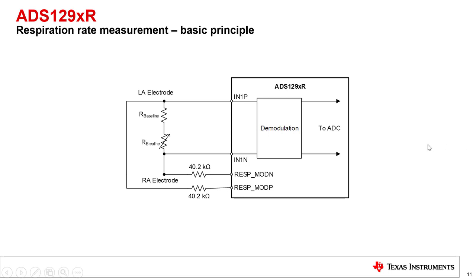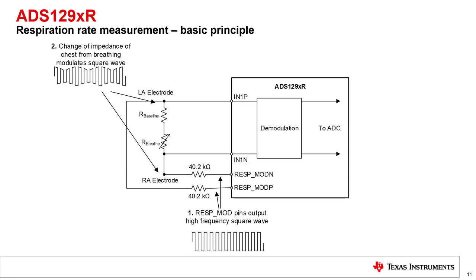First, the ADS129XR device outputs a high-frequency square wave excitation signal on the respiration modulation pins. The change in impedance of the patient due to breathing will modulate the amplitude of the square wave. Second, the channel 1 input senses this amplitude modulation waveform. Finally, inside the ADS129XR, there is a demodulation circuit that will remove the high-frequency square wave. This will leave only the low-frequency waveform that corresponds to the patient's breathing.